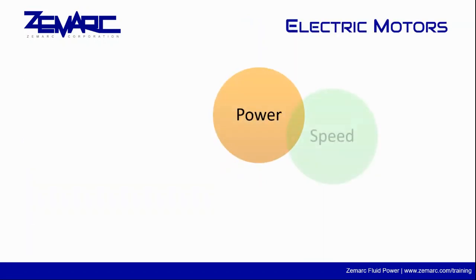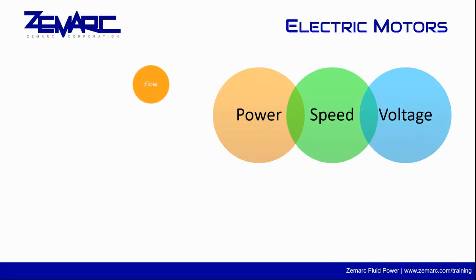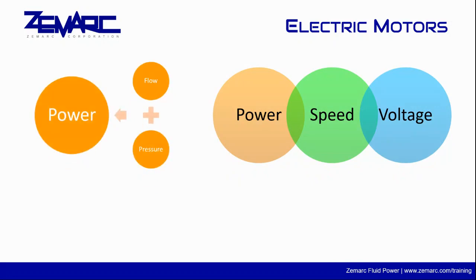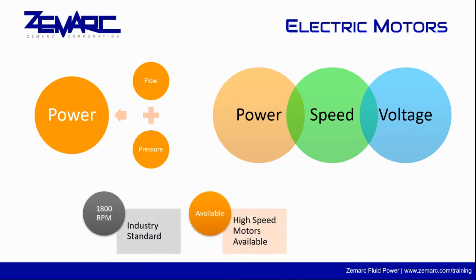As for electric motors, they're selected based off of their power, speed, and voltage. Power is determined by the flow and pressure of your system. 1800 RPM is industry standard for high-speed, but high-speed motors are available. For systems where you need variable speed, variable frequency drives, known as VFDs, can be used.